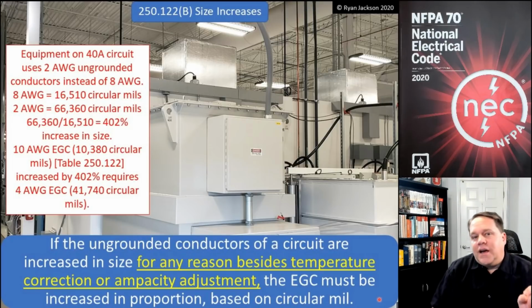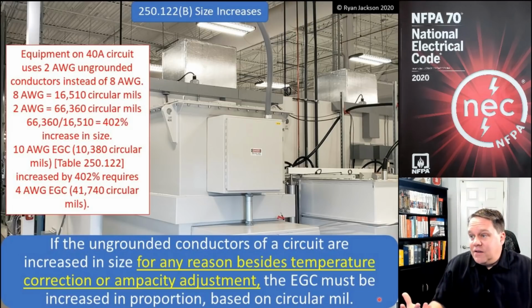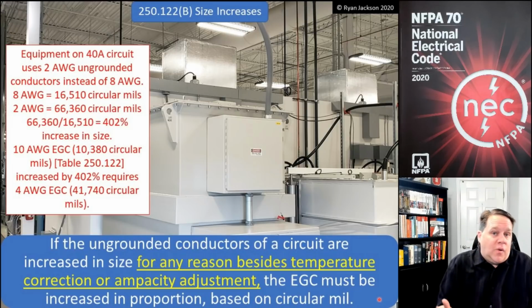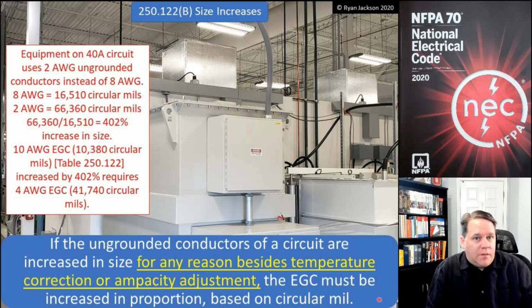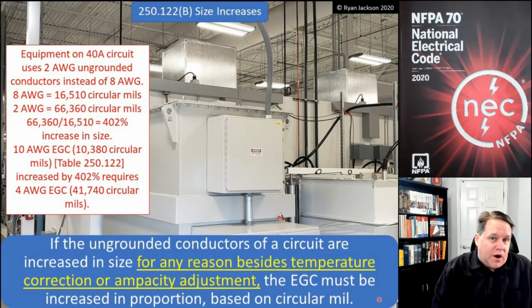Now think about it. 8-gauge NM cable has 8-gauge ungrounded conductors and a 10-gauge equipment ground. Is that right? So for a 40-amp circuit, it works great. But now I come back to trim out the house. They've installed the air conditioner, and I realize that it's only a 30-amp unit. All right, well, my 8-gauge wire is larger than what's necessary for the load. Now, did I increase it in size? Well, not intentionally. And do I have a problem? I mean, if I put it on a 30-amp breaker, is that 8-gauge wire going to trip the breaker in the event of a ground fault? Sure, it's not a problem at all.